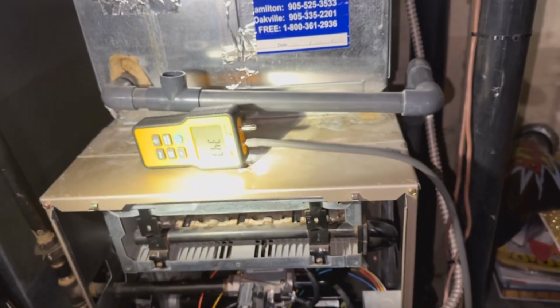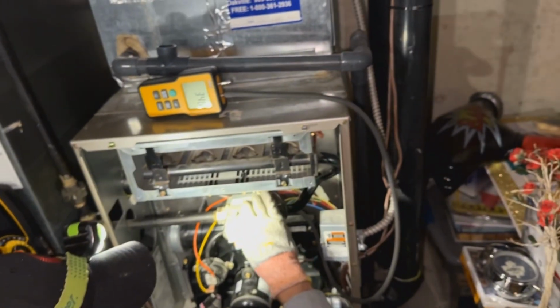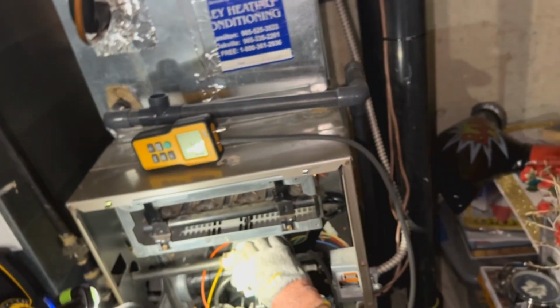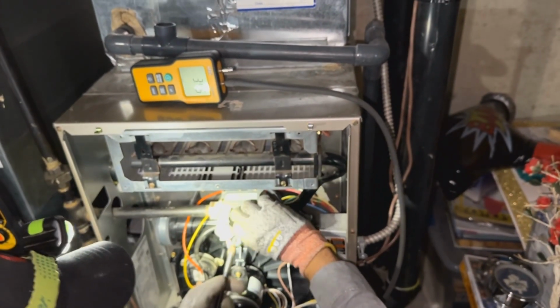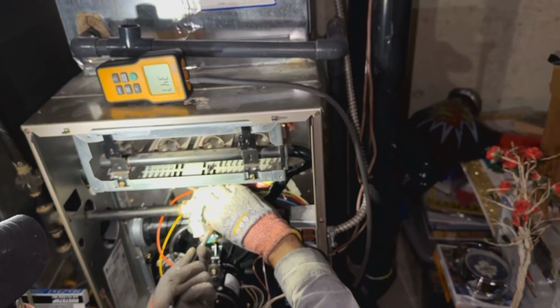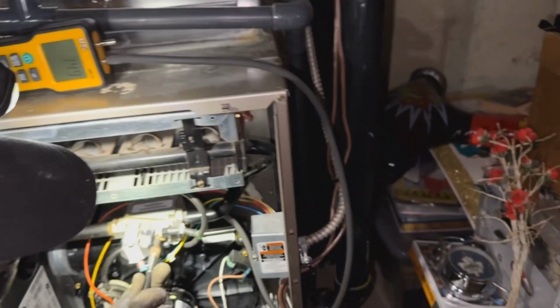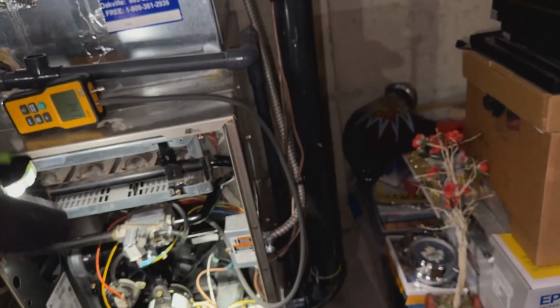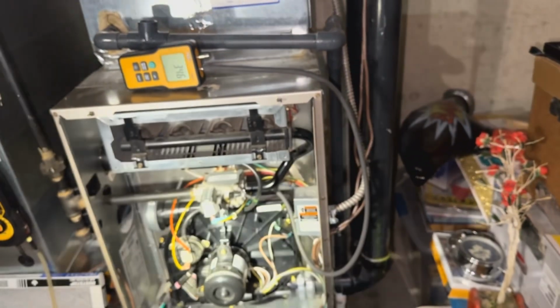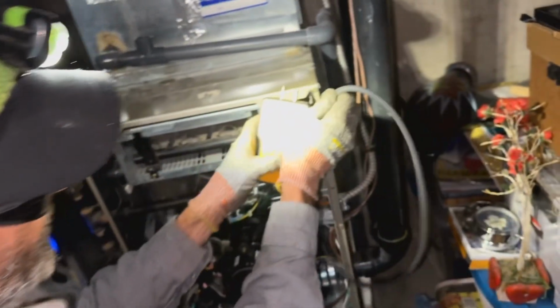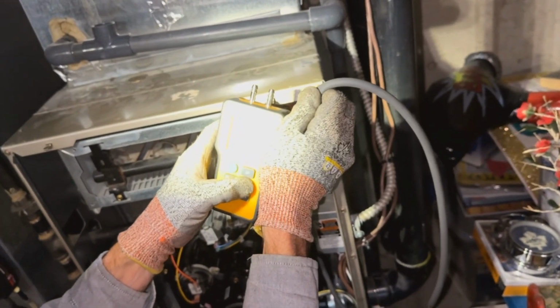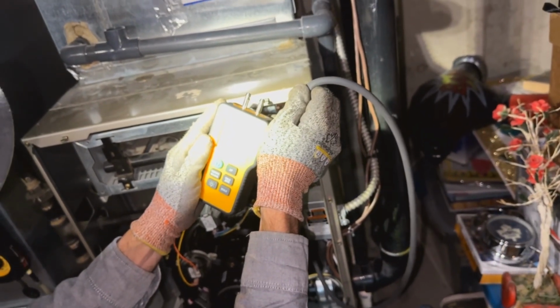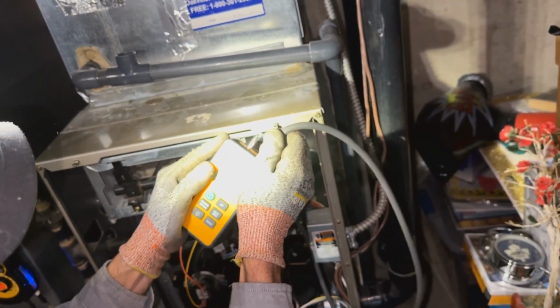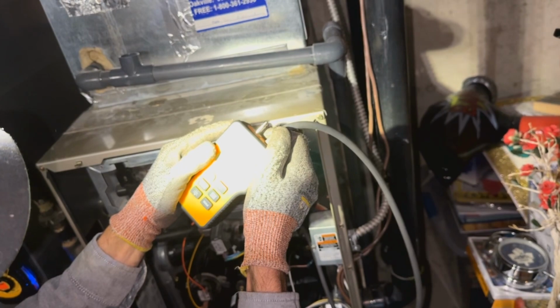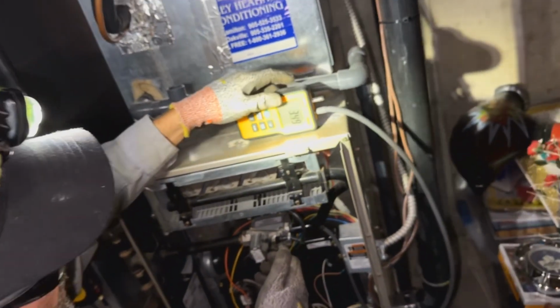There we go. So some furnaces like Carrier give a gas pressure range for manifold pressure. I like to keep it around 3.5, but as long as it's within manufacturer specs, you're all good to go. Just snug that. I didn't do it tight on you, Joe. So we'll just tear this once again just to confirm. I think my meter might be whacked. Pretty darn close to 3.5.